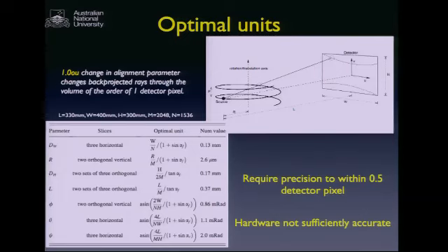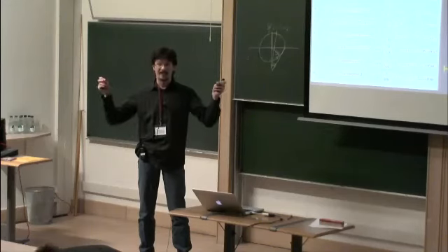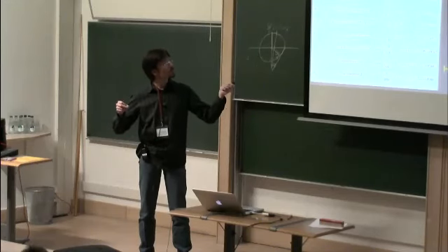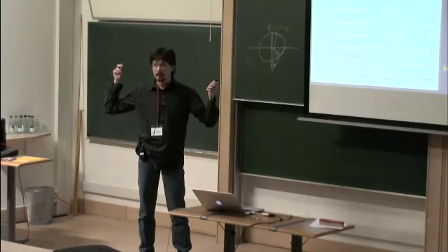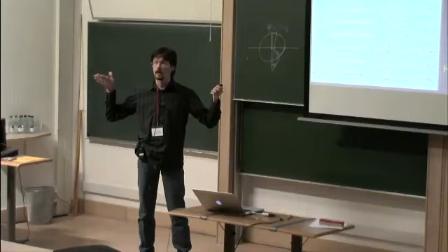Sample distance, on the other hand, we need to know to 2.6 microns. And that's quite tough, in particular since that's the distance between the rotation axis and the spot inside the gun where the X-rays stem from.